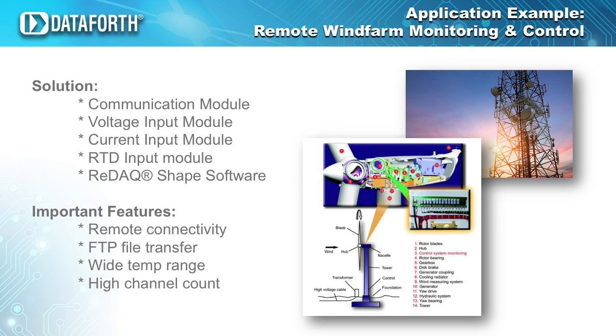A key aspect critical to wind turbine safety is wind turbine control. Without effective control, wind turbines can speed up in high winds, producing much higher yields than their rated power. Overspeed will also result if critical components fail. For example, if the generator overheats or is disconnected and therefore stops the braking action on the rotor's rotation. Wind turbines generate high voltages and currents. Electrical components within a turbine must therefore be able to withstand high surge voltages and be immune to the electrical noise that can radiate from generators and switch networks.